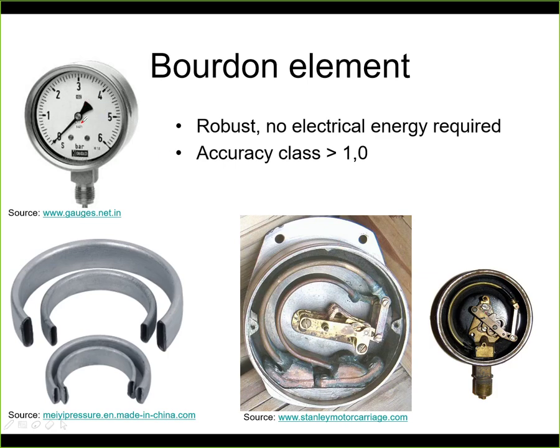Here on this picture on top left you have the whole instrument. So here is the needle, we have the scale, and behind the scale there is this mechanism with the Bourdon tube. Now typically the Bourdon pressure gauges do not have any electrical output. So you mount the instrument in your application, you locally read the pressure, and you don't have any electrical output.